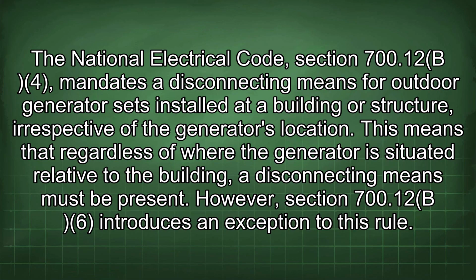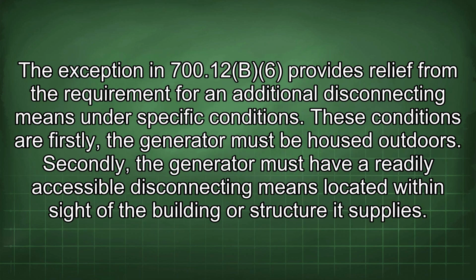The National Electrical Code, Section 700.12(B)(4), mandates a disconnecting means for outdoor generator sets installed at a building or structure, irrespective of the generator's location. This means that regardless of where the generator is situated relative to the building, a disconnecting means must be present. However, Section 700.12(B)(6) introduces an exception to this rule. The exception in 700.12(B)(6) provides relief from the requirement for an additional disconnecting means under specific conditions.